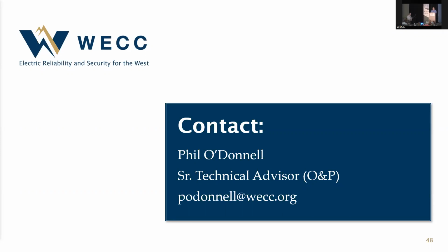But we'll just go down based on the ratings here. The highest rated one here may just go to some methodology questions, but interested in your thoughts. You say the nameplate is the gold standard, but how would I reconcile a case where I have a breaker nameplate rated at 1200 amps with the line rated for 1200? What do we rate an old 1200 amp breaker with limited info to match a dynamic line rating that would exceed the 1200 amp breaker nameplate rating?